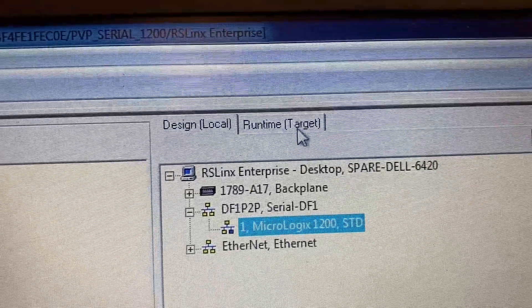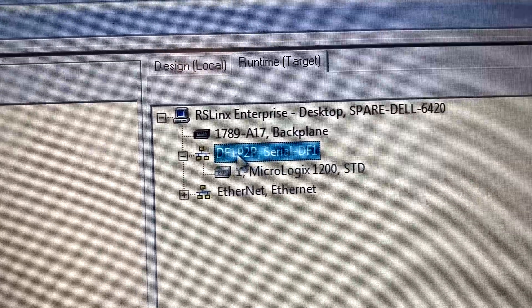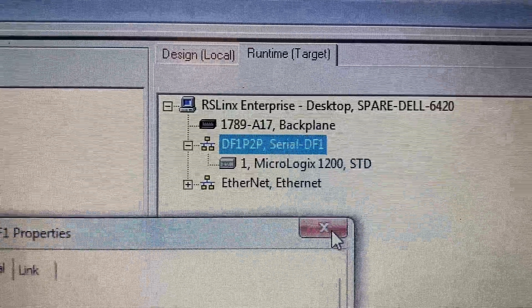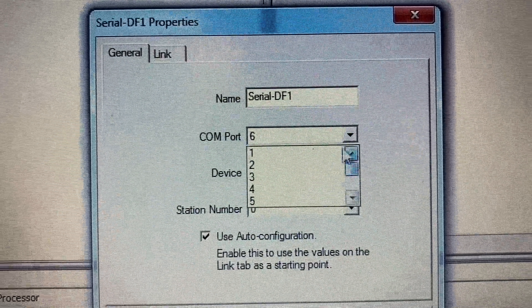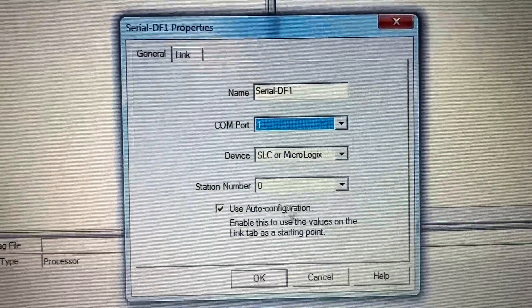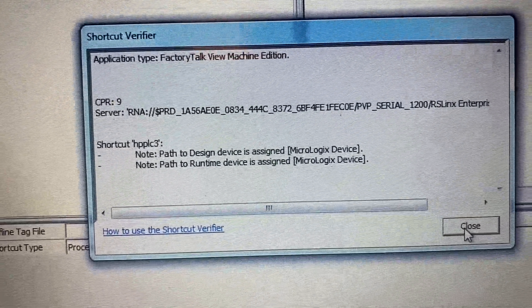Go to Runtime Target, right-click on DF1 P2P and select Properties. Then change the COM port back to COM1, because COM1 is the port on the HMI itself. Click OK, then Verify, then Close, then OK.